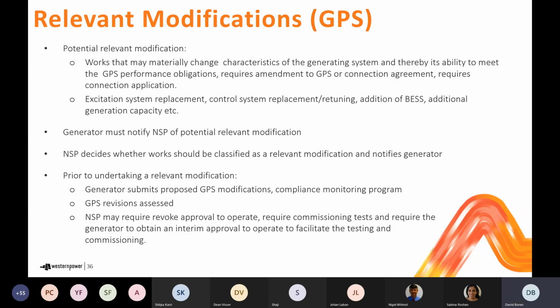Depending on the extent of, say, reworking and retuning of control systems, that might also be a relevant modification. You might consider adding additional capacity to an existing generating system by adding a STATCOM, adding a BESS, or, in the case of renewable generators, adding additional turbines or PV arrays. All of these things would change your ability to meet previously stated generator performance standards, and therefore are likely to be relevant modifications.